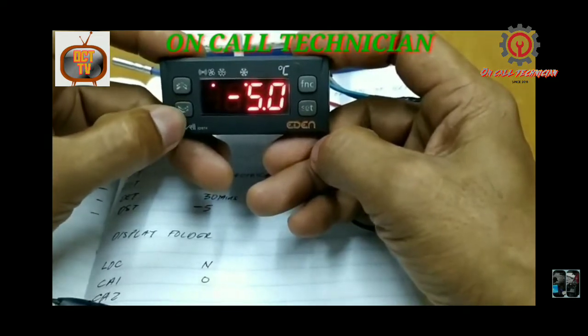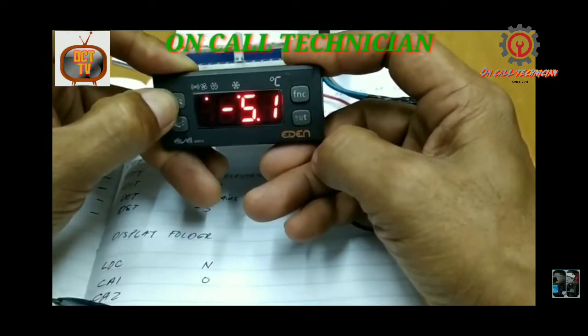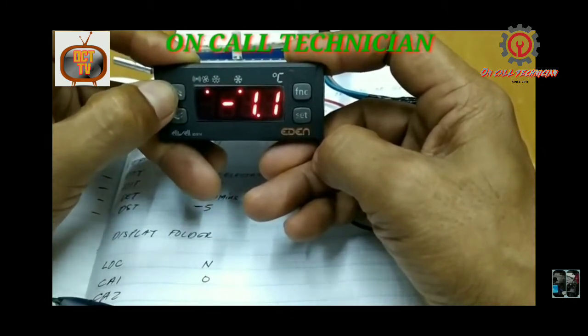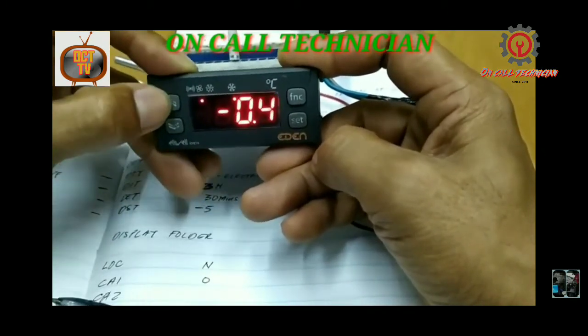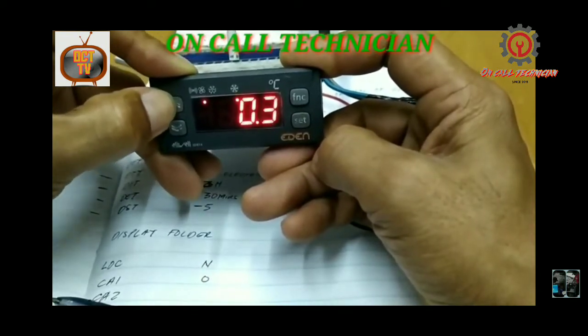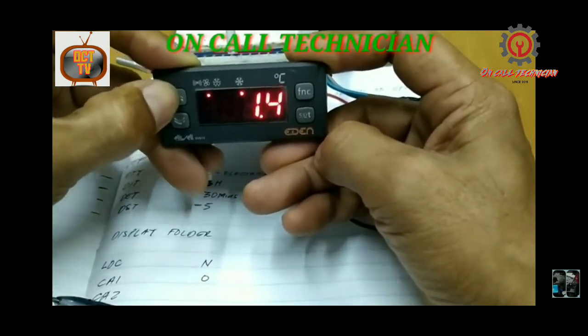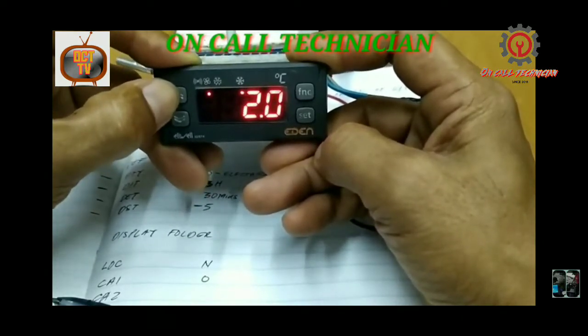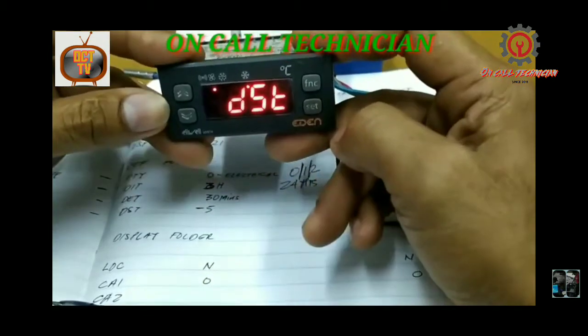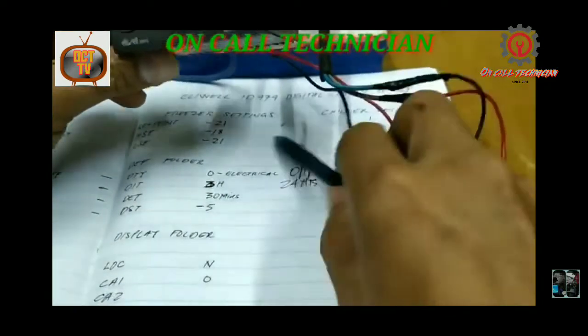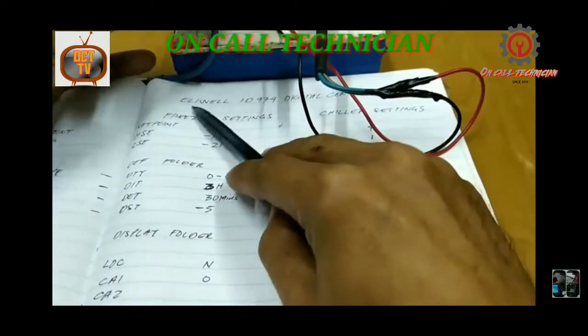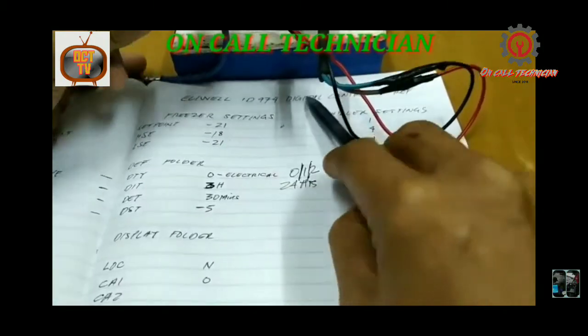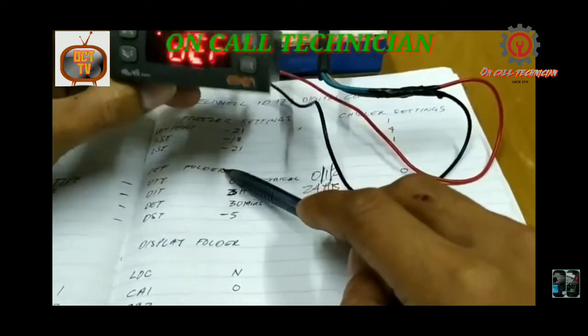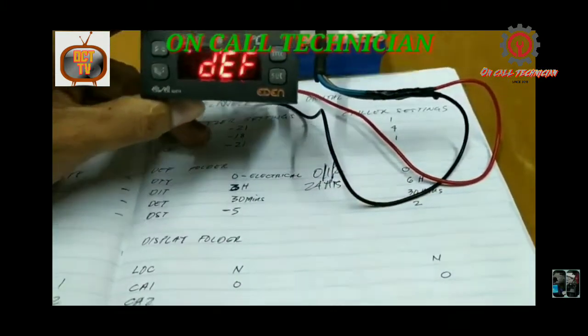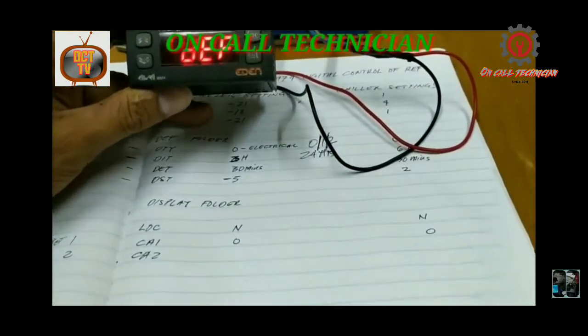Okay, just press the arrow up button to increase the temperature from -5 to +2 degrees Celsius. Okay, so it's up to you. You want 3, no problem. You want 1, no problem. So press set to memorize. So it's done for the DEF folder. Okay, so remember, guys, the freezer setting and chiller setting is different. Okay, so what else?